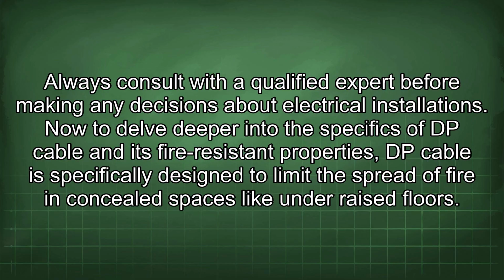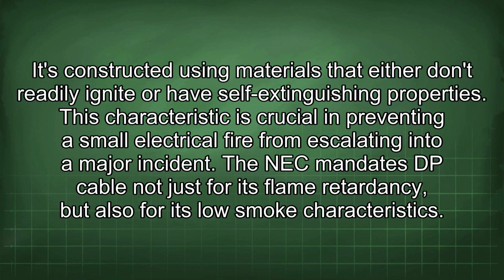Now to delve deeper into the specifics of DP cable and its fire-resistant properties. DP cable is specifically designed to limit the spread of fire in concealed spaces like under raised floors. It's constructed using materials that either don't readily ignite or have self-extinguishing properties. This characteristic is crucial in preventing a small electrical fire from escalating into a major incident.